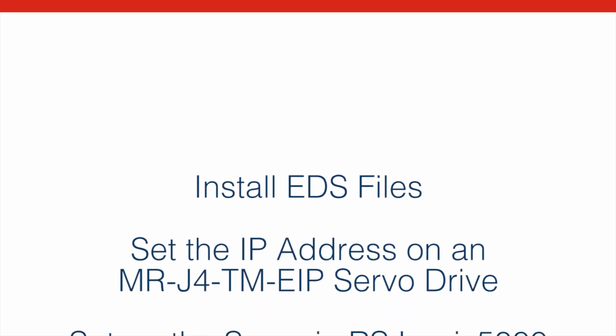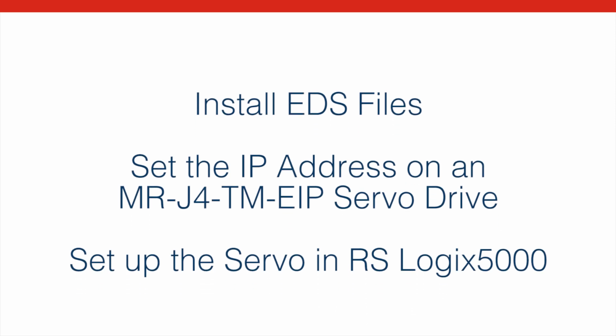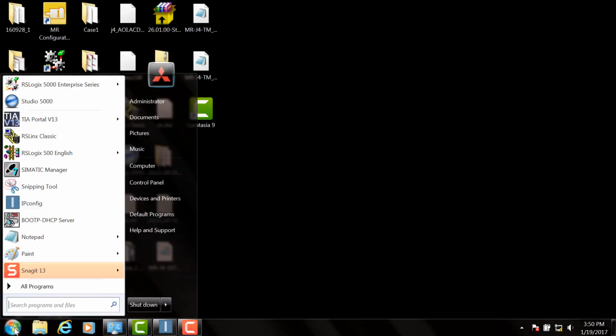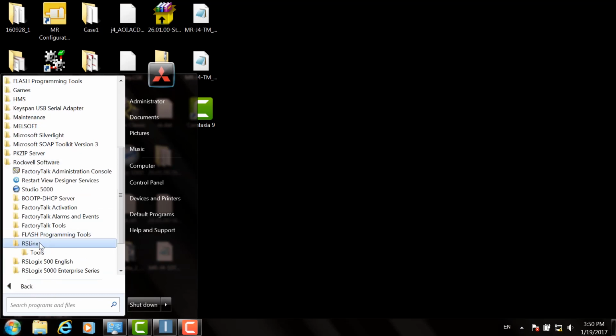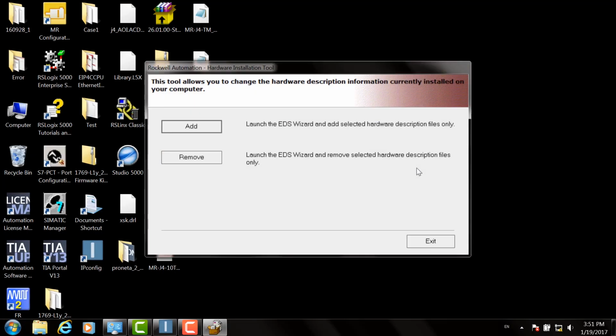In this video, we're going to show you how to install EDS files, how to set the IP address on an MR-J4-TM-EIP servo drive, and how to set up that servo drive in RSLogix 5000 to work with the AOIs. Open Rockwell Automation's EDS wizard from All Programs, Rockwell Software, RSLinx, Tools, EDS Hardware Installation Tool.